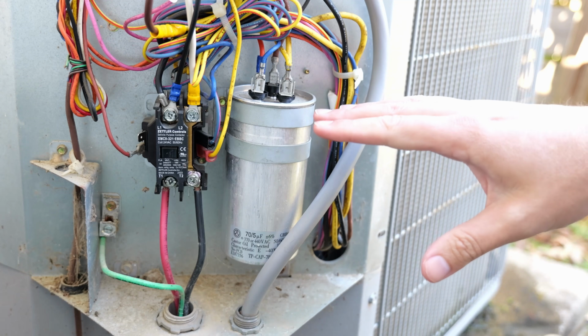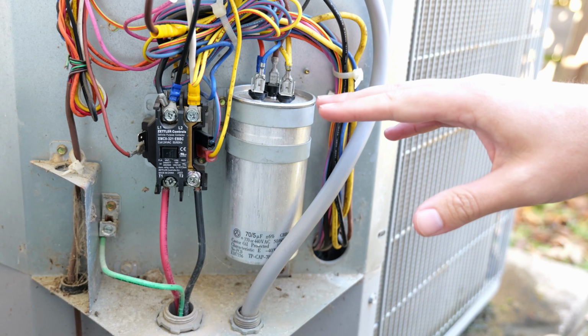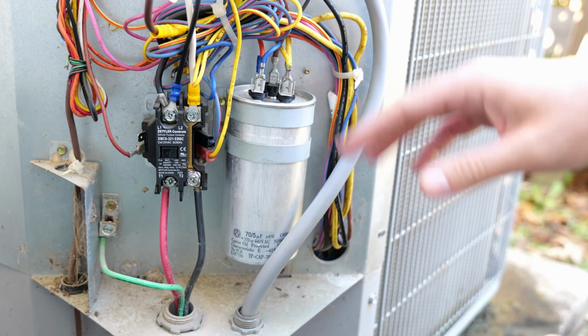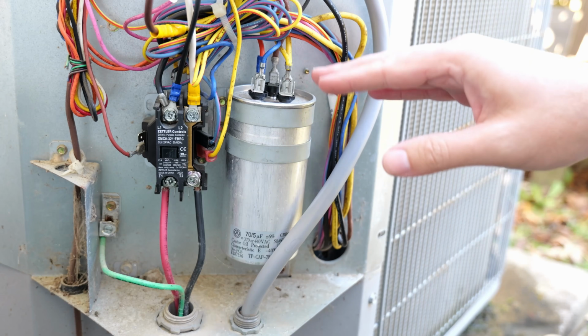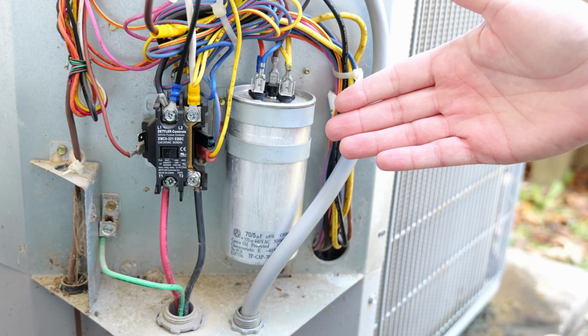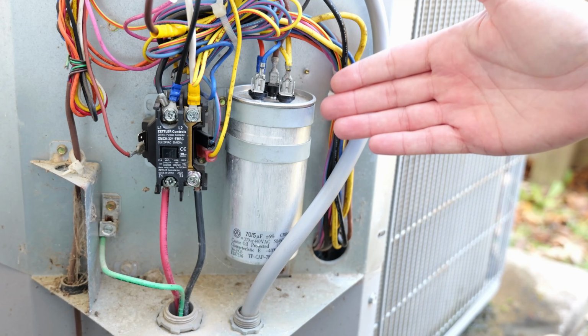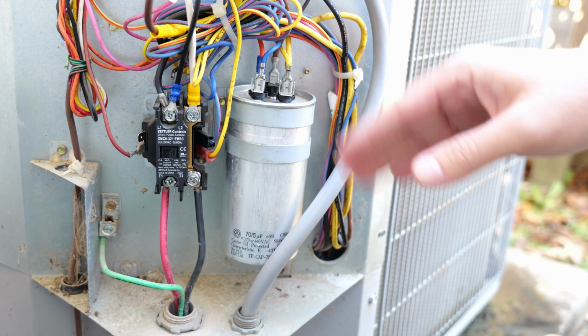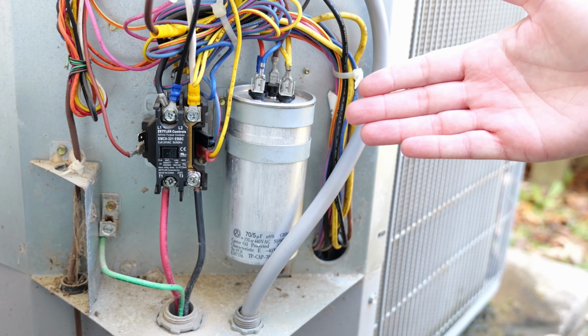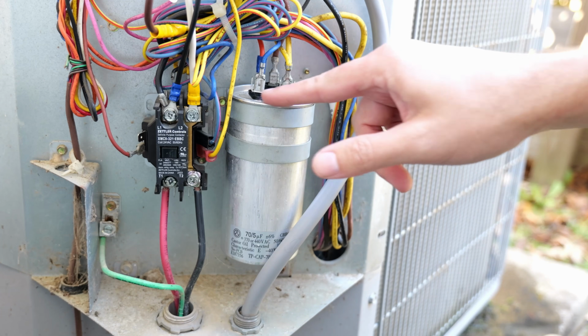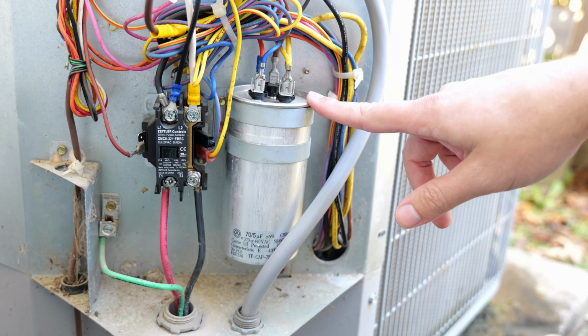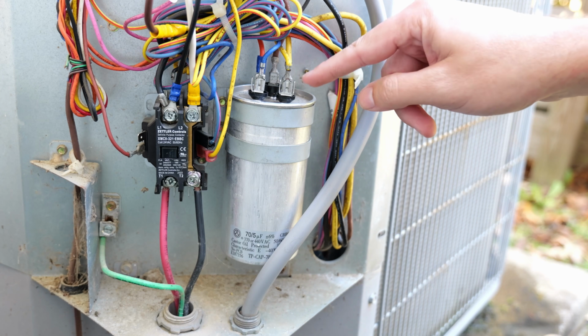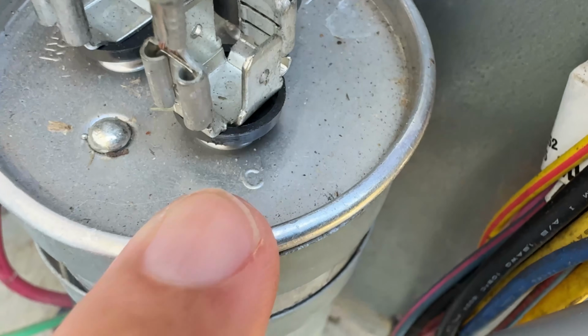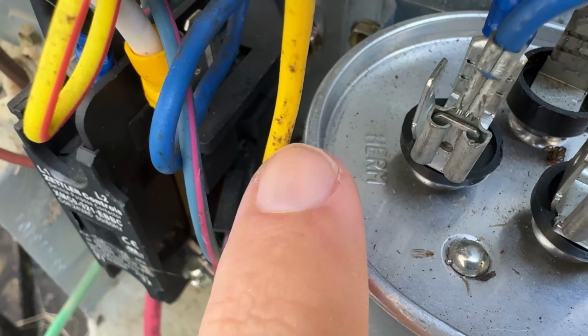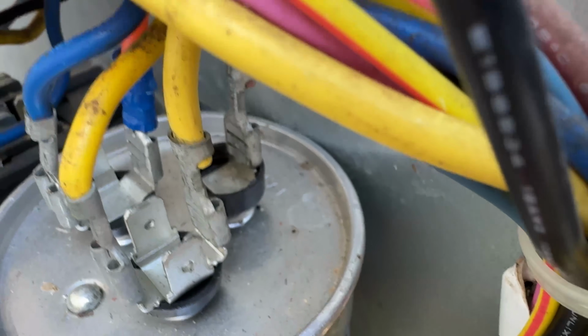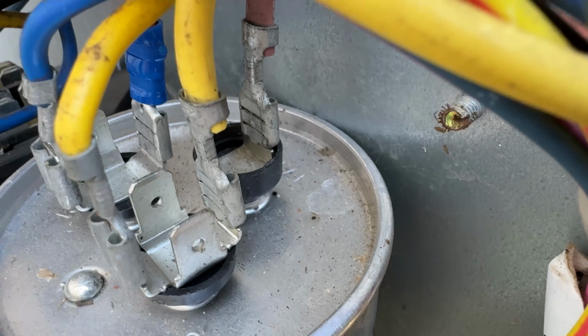The next thing I always recommend doing before you start touching these terminals and removing wires is make yourself familiar with where each of the wires go, because if you have to replace it, the wires are going to go on the same terminals that they are currently on the old one. So what I always recommend is you can look at the top of the capacitor, and most of the time there's going to be some sort of labeling where this says C, which is for common. You'll see HERM for the HERM, and then most of the time you'll also see fan for the fan terminal.